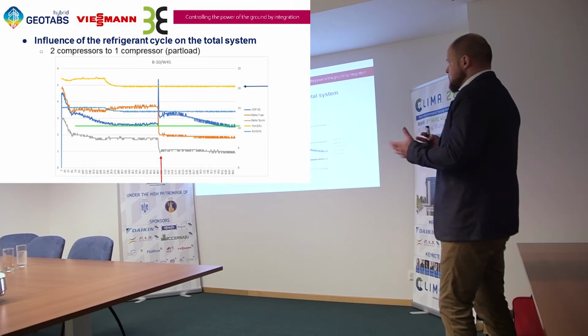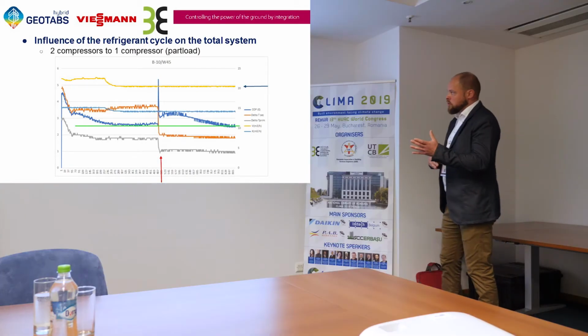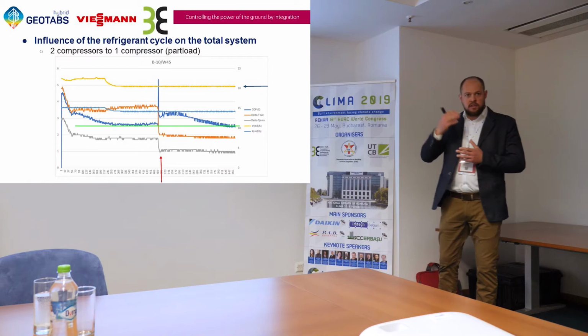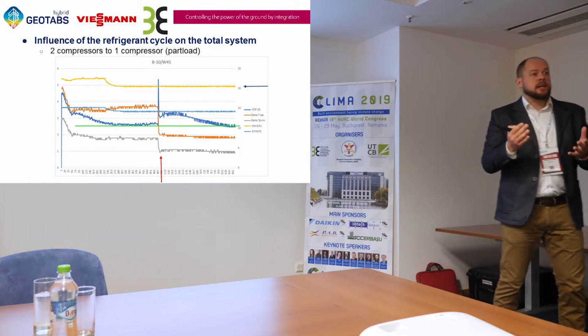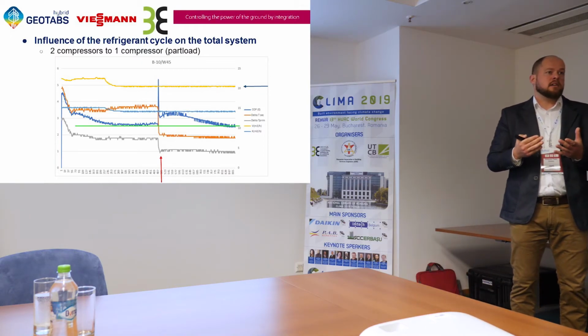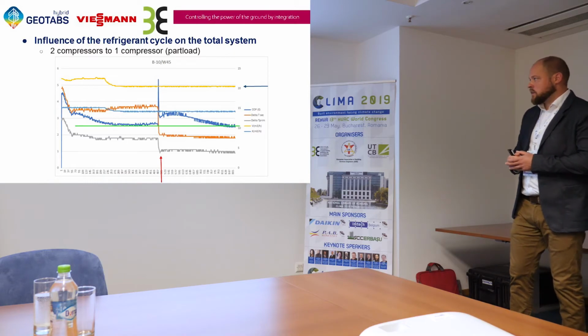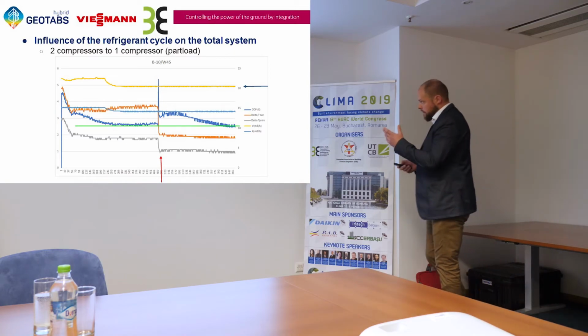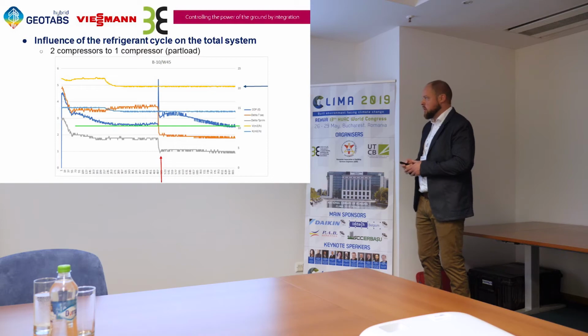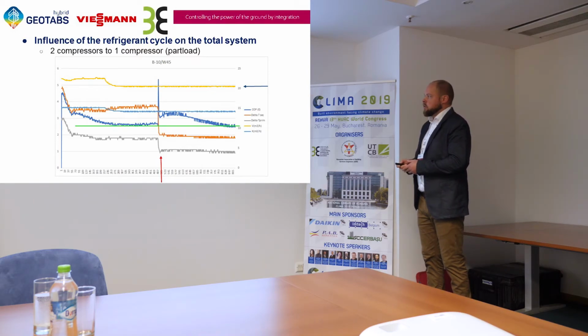Now, what's the influence of running on two compressors or on one compressor? It's often thought that when we run on one compressor, we have a bigger evaporator, so the COP will be higher. We have done a lot of tests in the field, and also at our laboratory, and you can see that it's not that big of a difference.